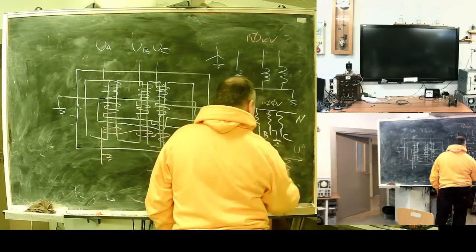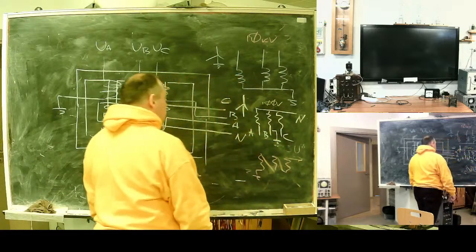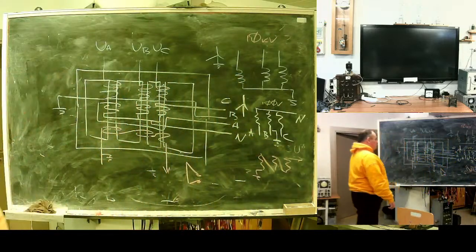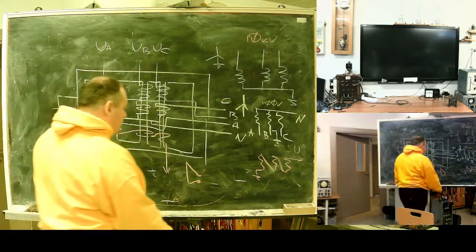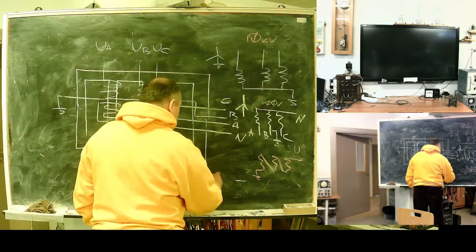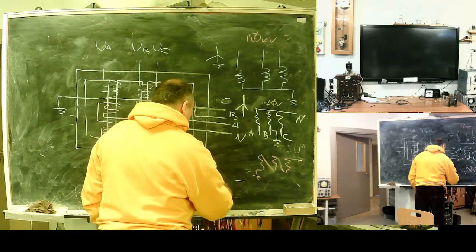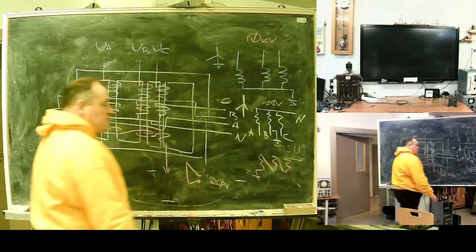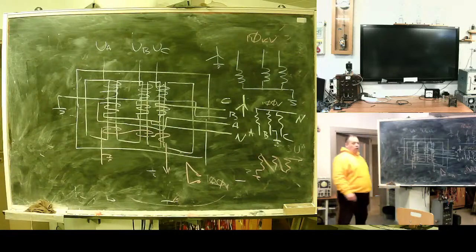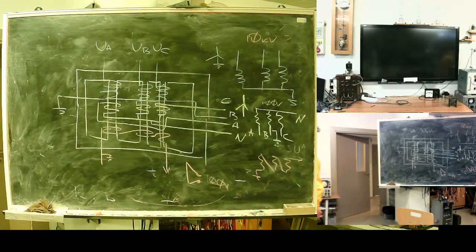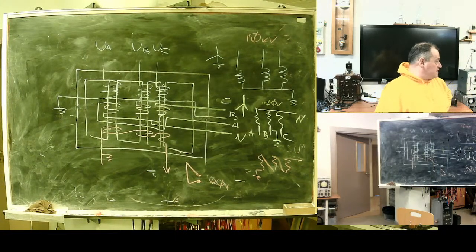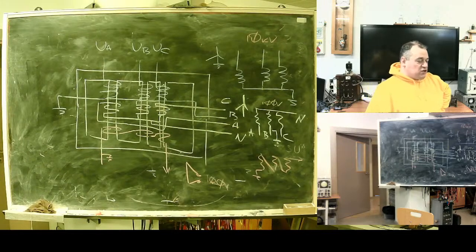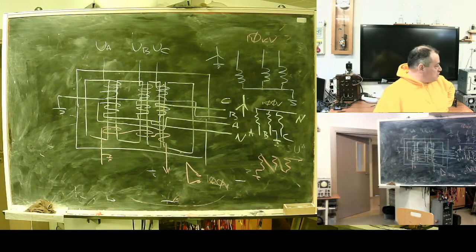U0. They have a triple U0 winding with nominal voltage 100 volts. In case of earth fault, voltage at this winding will be 100 volts. All these old school barrel transformers do have an additional winding for zero sequence voltage.